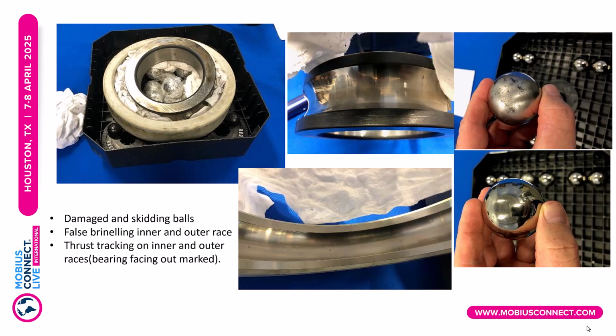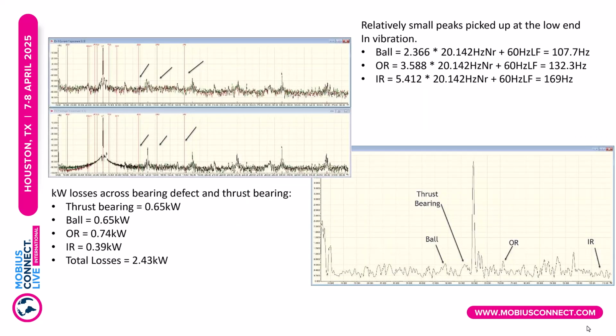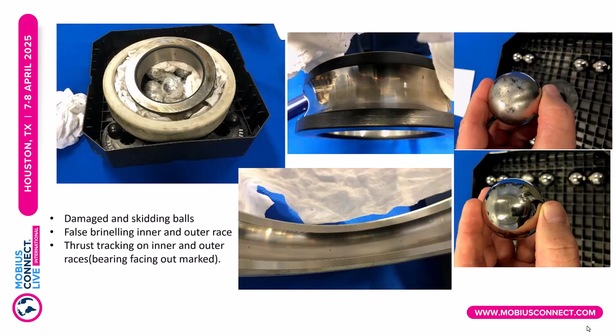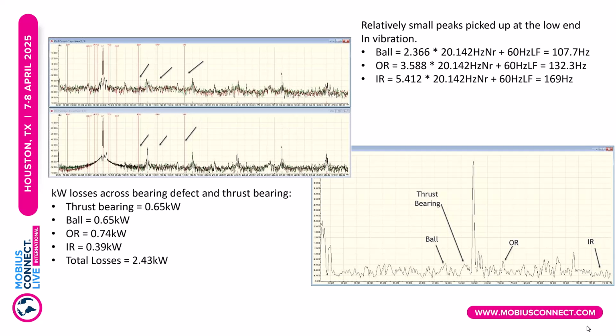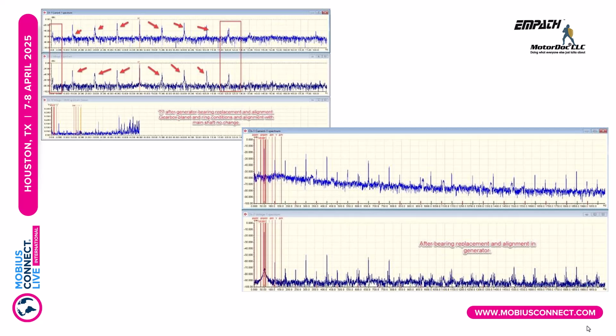So when we took it all apart and took a look at it, the inner and outer race peaks were very small, but you can see the false brinelling on the inner and outer race. And then the ball, which was the higher peak, you can see that one of them had smeared a little bit, meaning it got caught in the cage, which is part of the reason I wanted the cage. So they replaced it and put the new one up there, and as you can see, they were able to retest it. They dropped from 11 kilowatts to 2.4 kilowatts of total losses for all of those bearings. And they still have a gearbox issue.